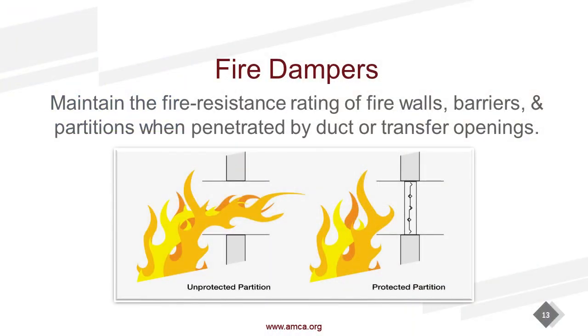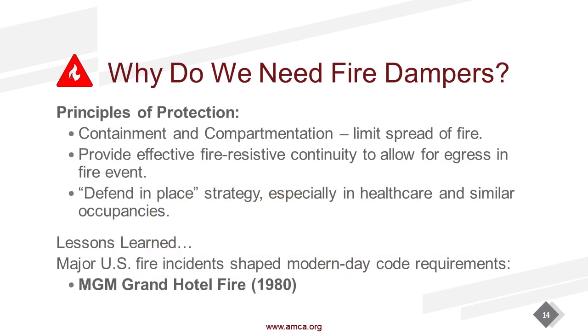So as I mentioned earlier, that is the reason why we put fire dampers. You have an unprotected partition, flame will pass through it. When you protect it, it stops the spread of that fire. We know we need them. Containment and compartmentation, they just told you about them. But unfortunately, what they say is necessity is the mother of invention, right? Not for life safety. Unfortunately, we need tragedy to see change.